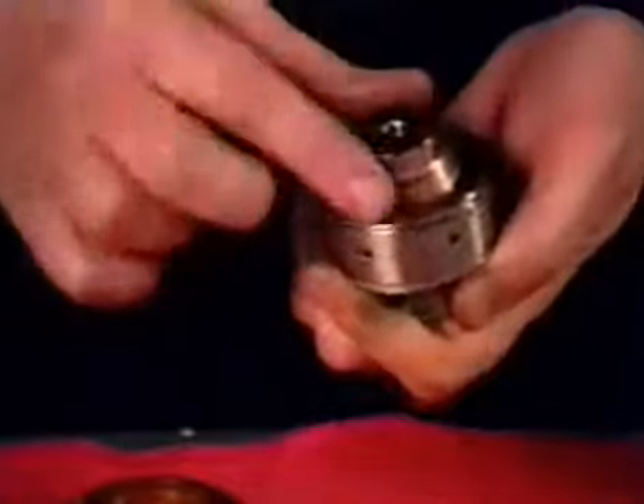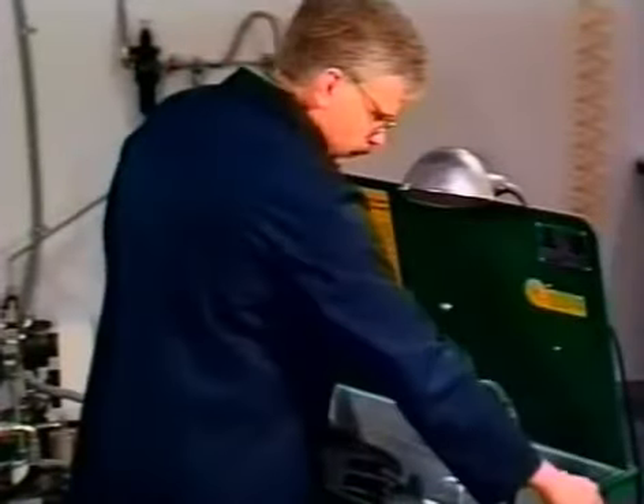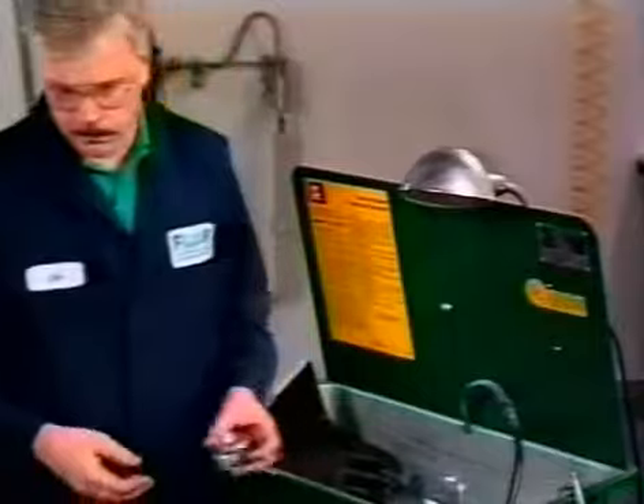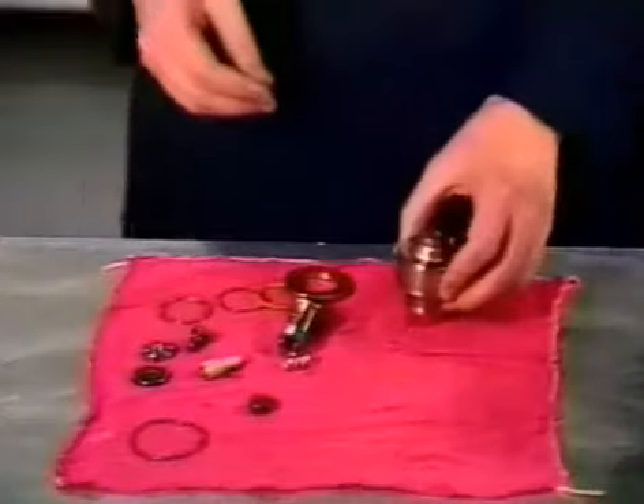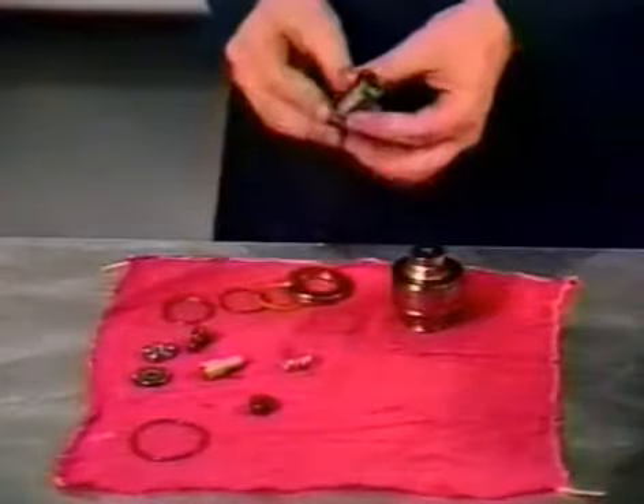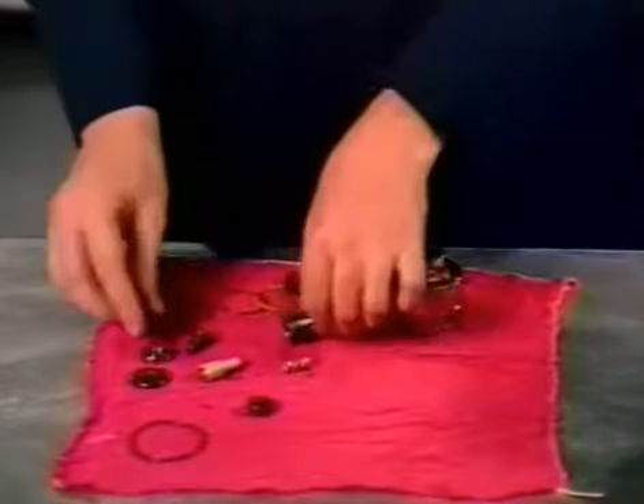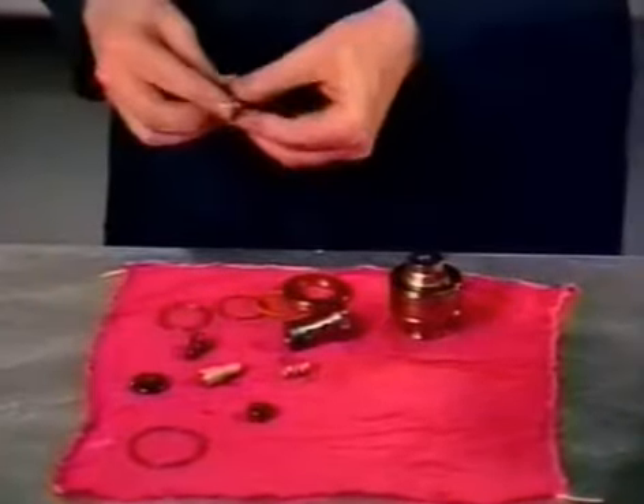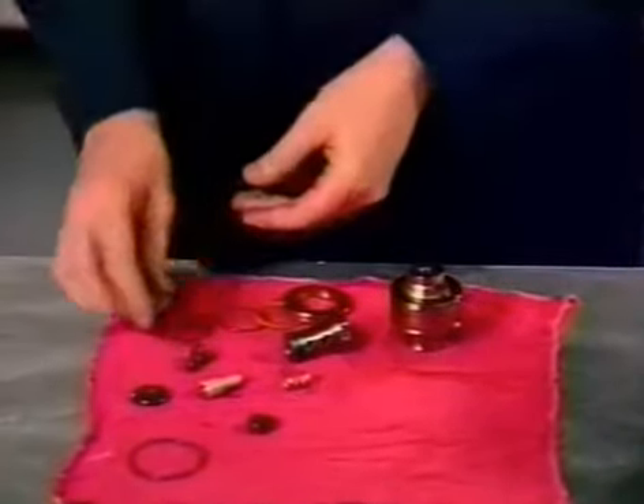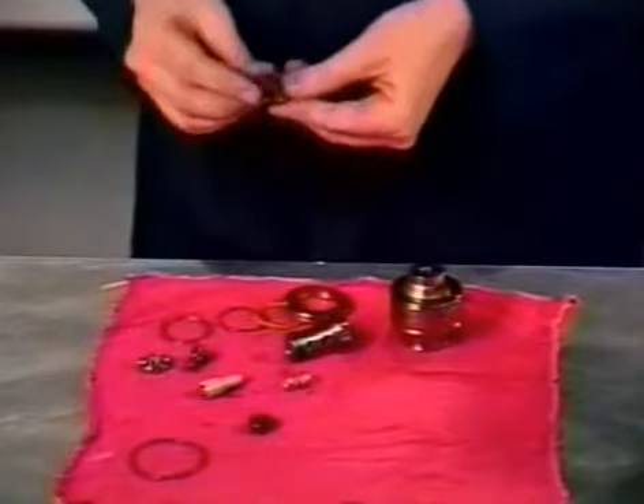Clean the check valve body using solvent and compressed air. If the check valve has failed prematurely, replace only the damaged parts. If you're servicing the check valve at a regular interval, replace all the components in the check valve rebuild kit.